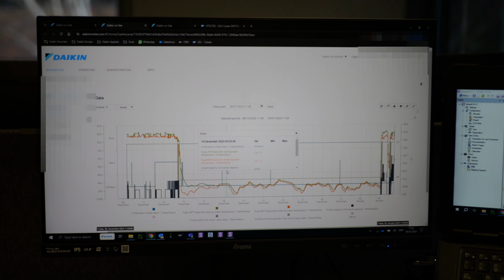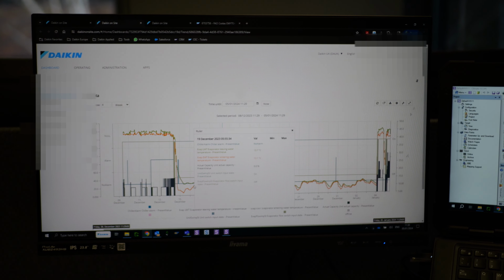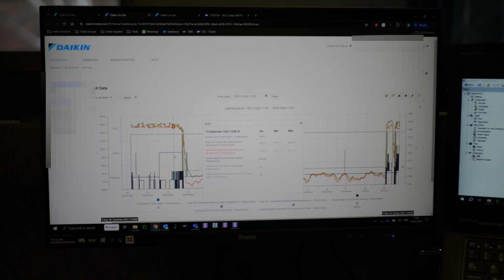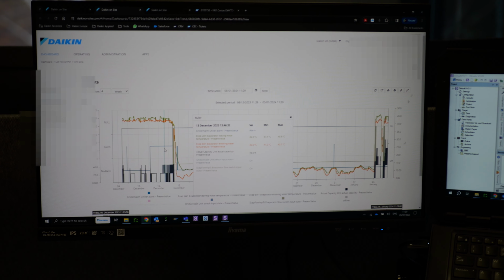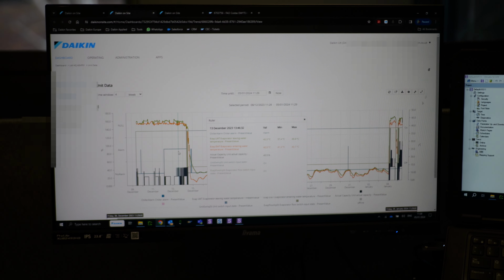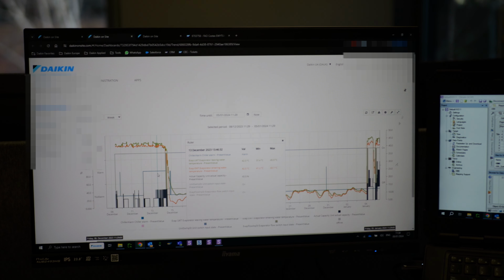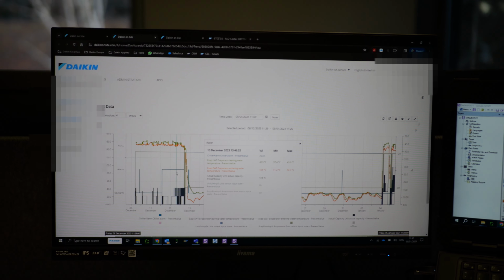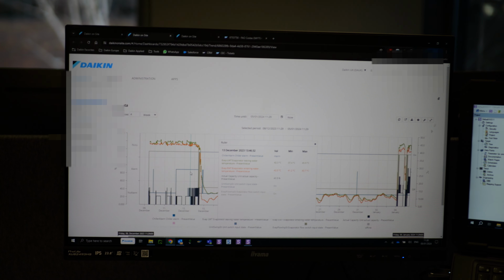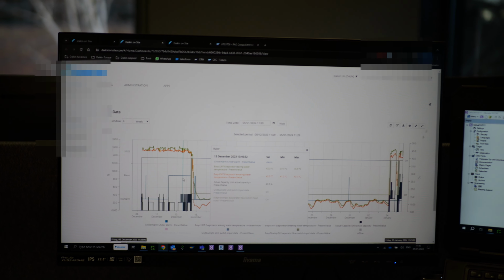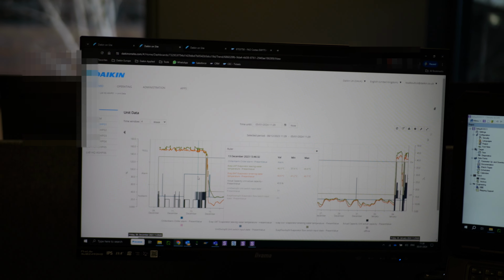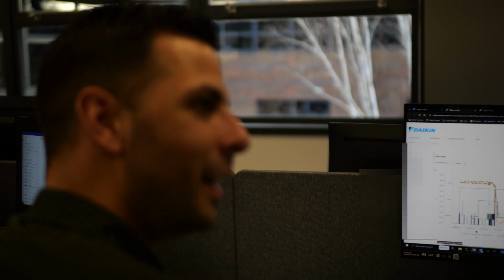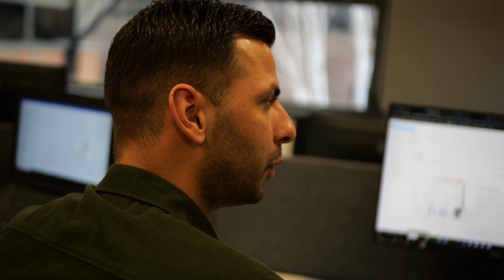Let me drag this down a little bit. There you go - you know why I love this? Because, and I'm sure you've had it on many sites, the amount of times we have issues with BMS with the pump switching off, then it trips on low flow, and the chiller doesn't reset because the BMS connection doesn't force it. The pump should always be initiated before the chillers, but what they tend to do is have them on at the same time. So what happens is they blame the chiller, and you say whoa, wait a minute.